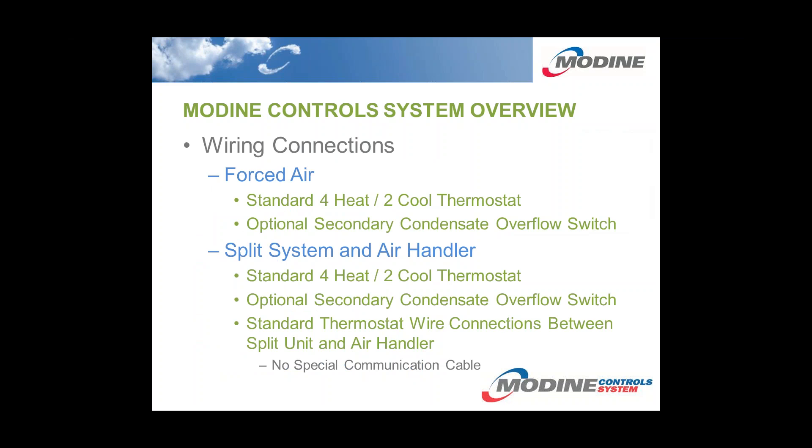Wiring connections are very simple. Here are a few different connections for a forced air unit. We use a standard four heat, two cool thermostat, two stages for the compressor, and two stages for the auxiliary electric heat. Split systems are very similar — there are no special communication cables required to go between the unit and the air handler, just standard thermostatic signals.